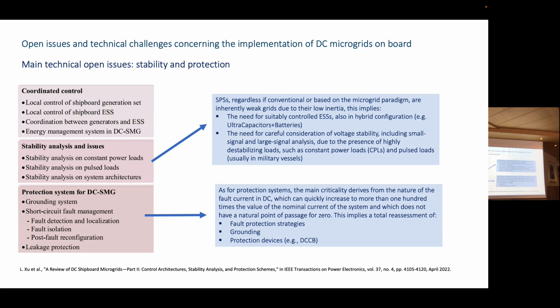This is especially important in the presence of certain kinds of loads, the so-called constant power loads and pulsed loads on board, even though pulsed loads are usually present mainly in military applications. As for the protection system, in DC systems fault current can reach more than 100 times the value of nominal current in a very short time.